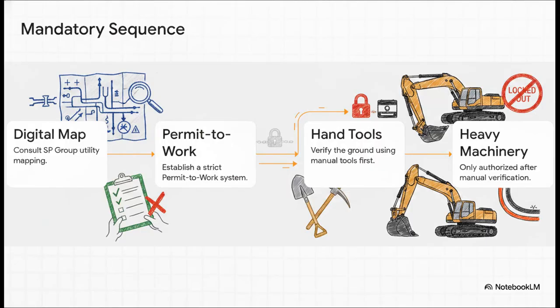You might be wondering, how do you legally and safely get to that final step of actually bringing in the heavy machinery? Well, there's a mandatory sequence of operations you've got to follow. First, you consult the SP Group Digital Utility Map. Second, you lock in a strict Permit to Work, or PTW, system. Third, and this is what we're really focusing on today, you absolutely must use hand tools to verify the ground. Heavy machinery, that is strictly step 4. It is legally locked out until the first 3 steps are totally complete. You simply cannot jump from looking at a map straight to firing up a machine.